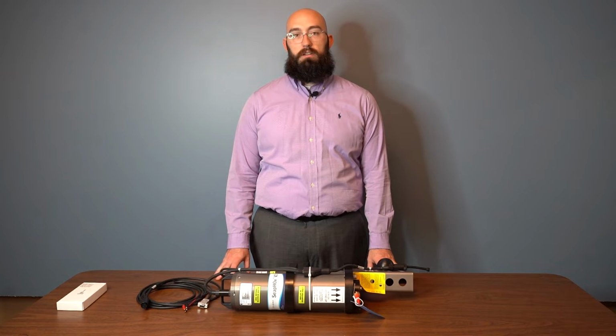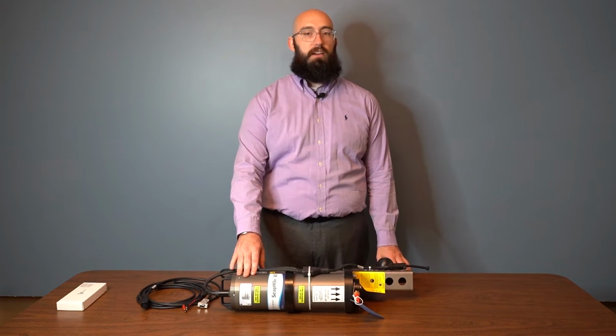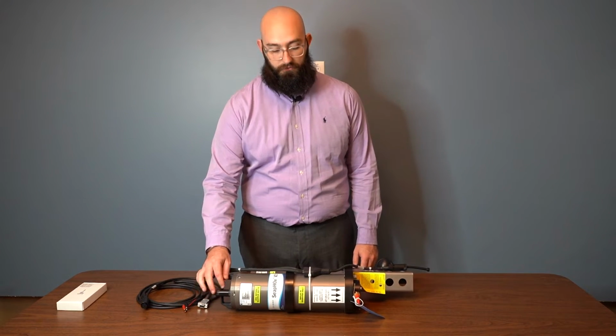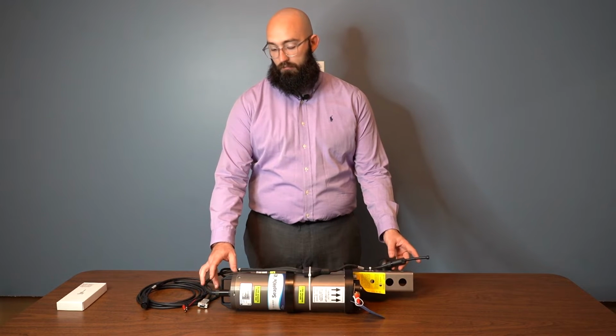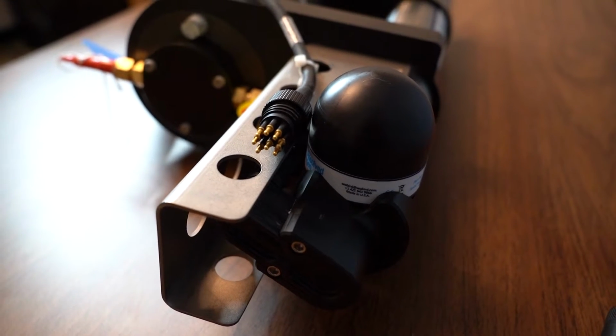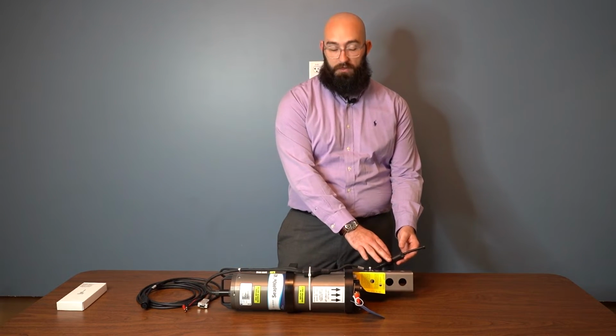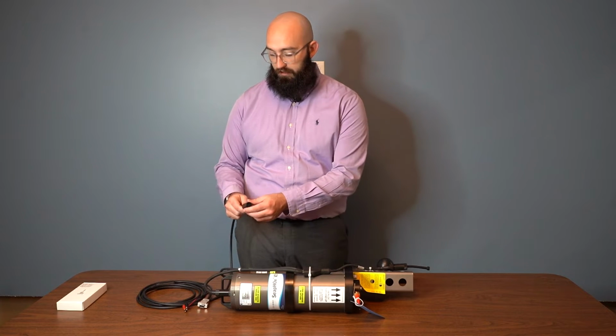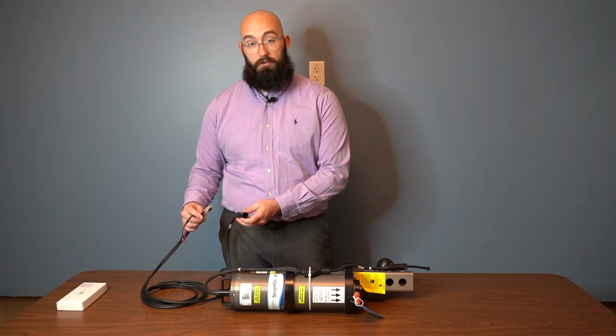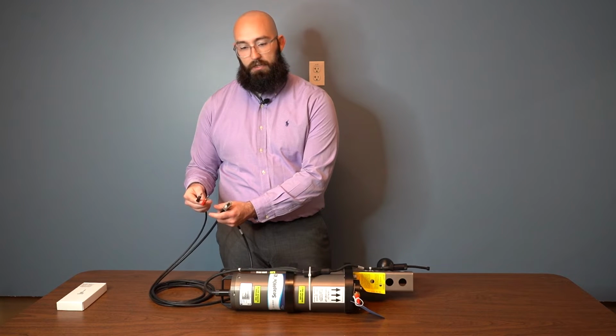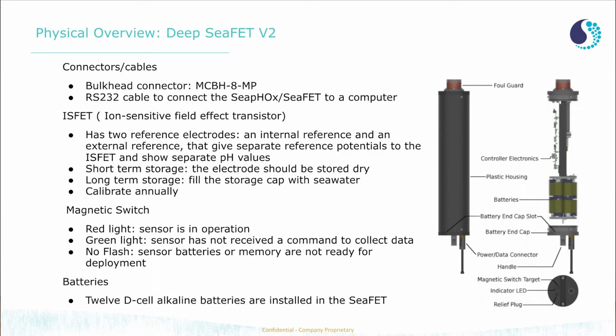So the Deep SeapHOx V2 is a multi-sensor system, so we'll begin by looking at the Deep SeaFET V2. The Deep SeaFET V2 is connected to the Y cable, which is a 8-pin male MCBH connector. Both ends of the Y cable on this side are 8-pin male, and that will connect to your PC via your 8-pin MCBH to serial RS-232 connector, as well as a pigtailed power supply cable. The Deep SeaFET V2 uses the SeaFET pH sensor technology, which is an internal reference and an external reference, which both give separate reference potentials to the ISFET and show separate pH values.